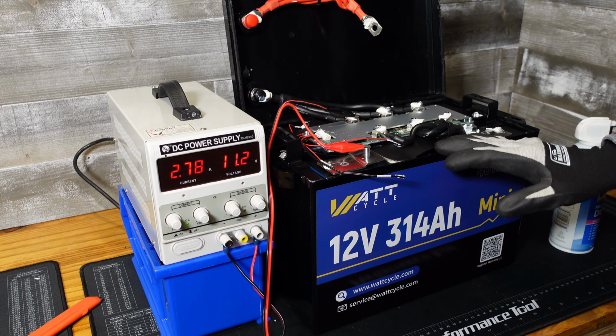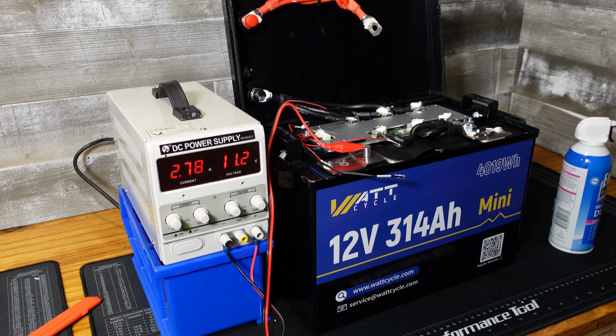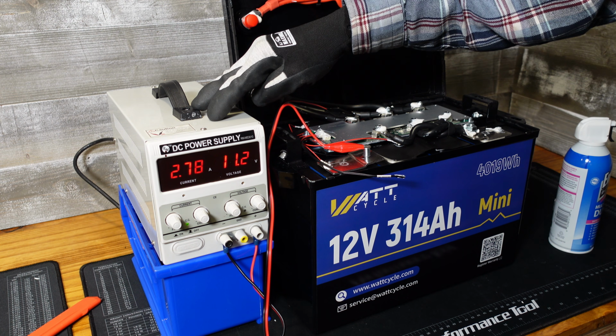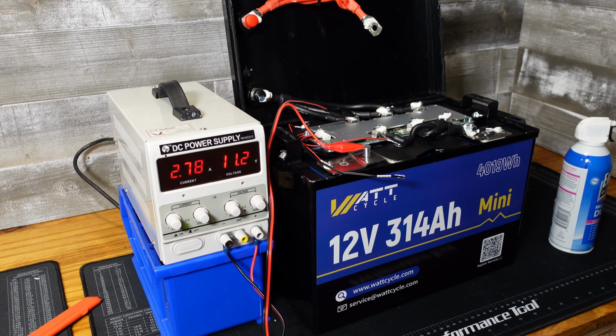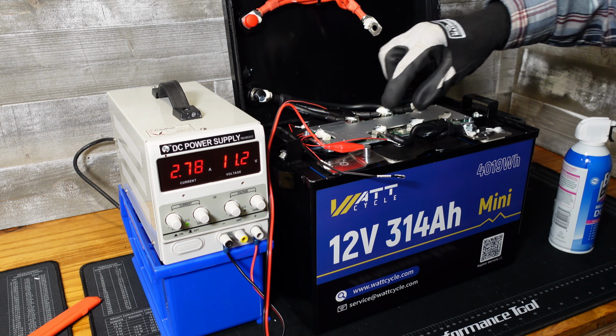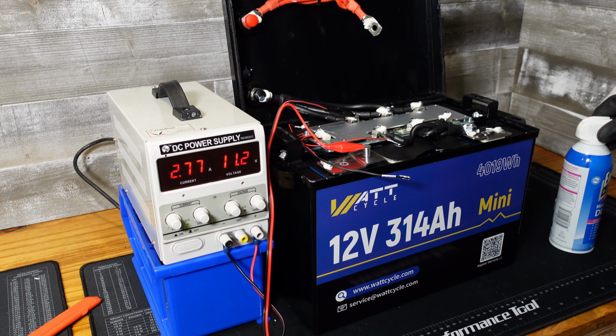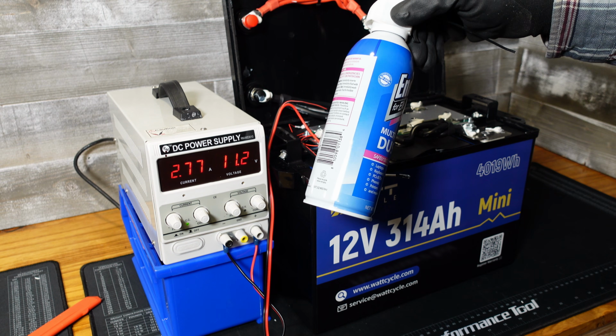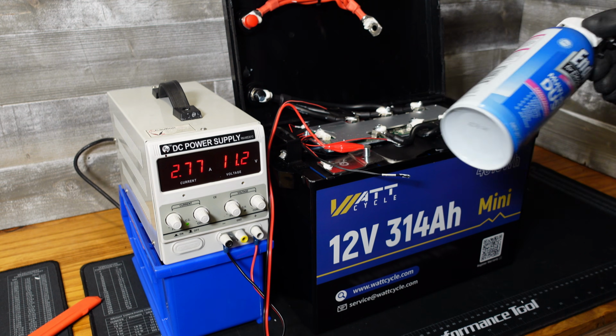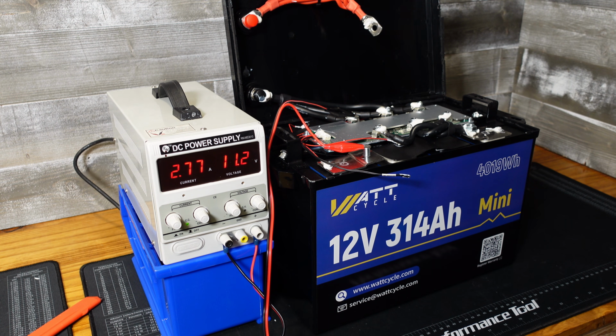The battery is put back together and we're ready to test the low temperature charge protection. I have a bench power supply here charging at 2.78 amps going through the BMS, and I have the temperature sensor pulled off. As per usual, I'm going to spray the temperature sensor with computer duster, which should drop it well below freezing and cause the charging to stop.